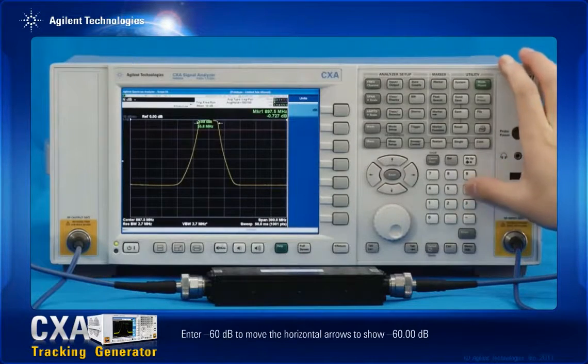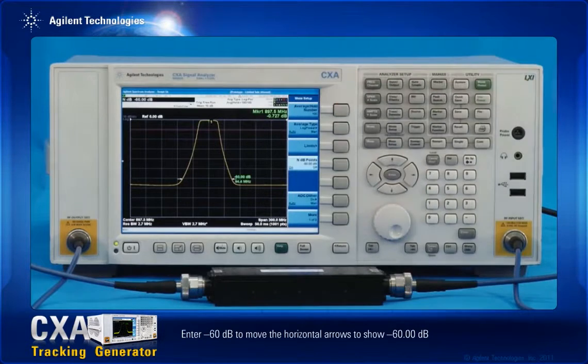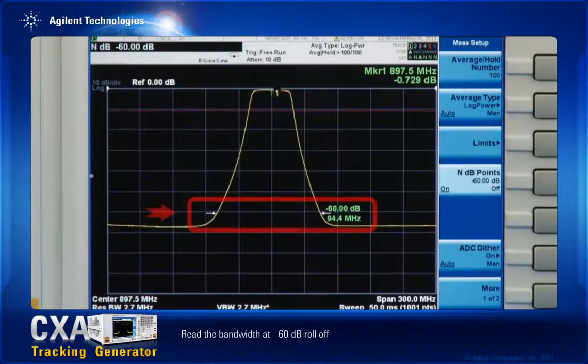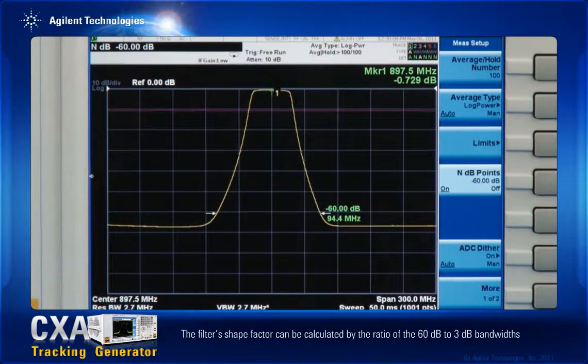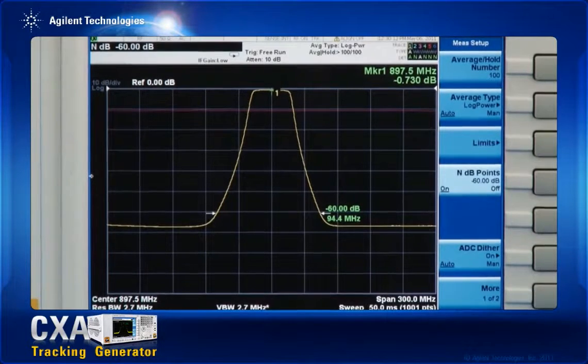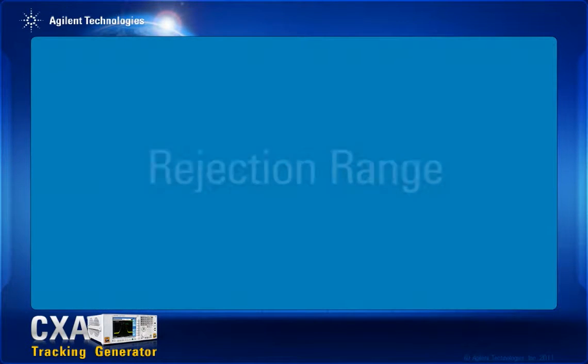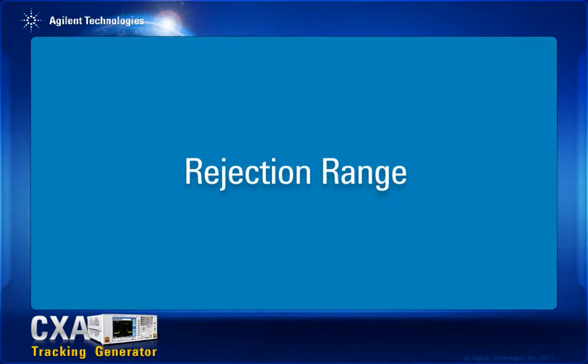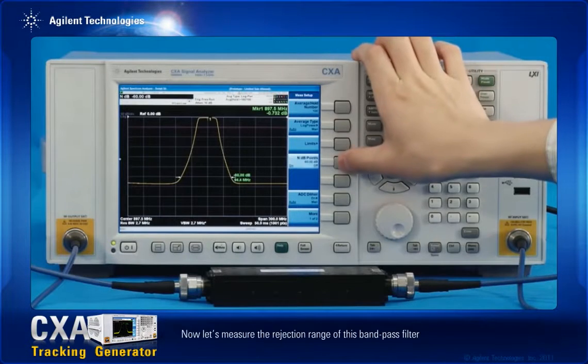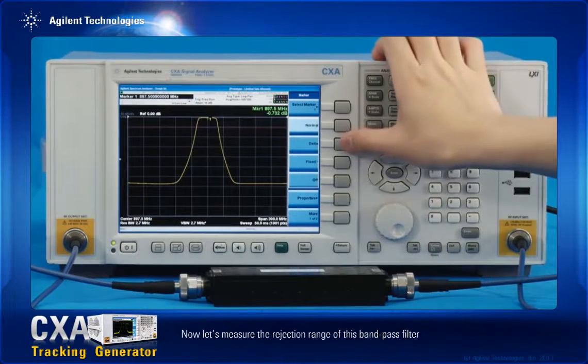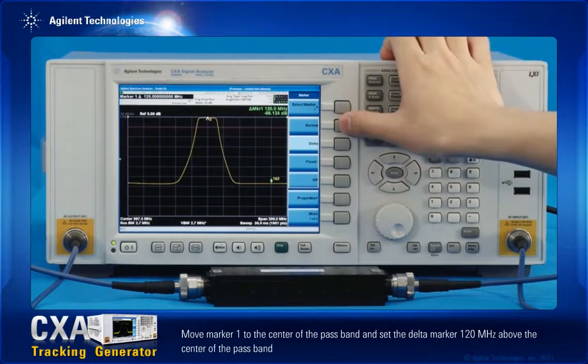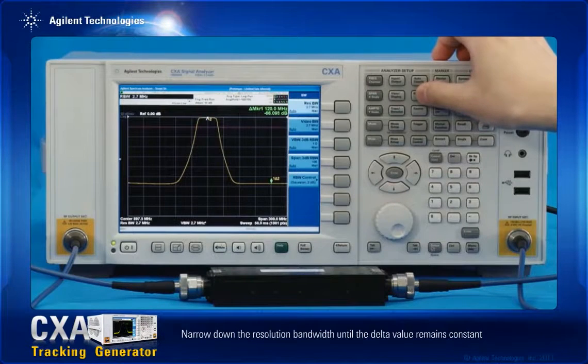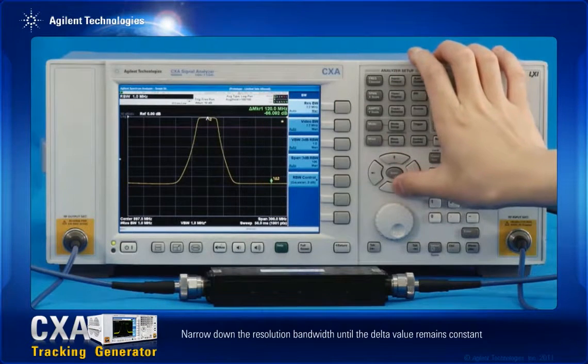Enter minus 60 dB to move the horizontal arrows to show minus 60 dB and read the bandwidth at minus 60 dB roll off. The filter's shape factor can be calculated by the ratio of the 60 dB to 3 dB bandwidths. To measure the rejection range of this bandpass filter, move marker 1 to the center of the passband and set the delta marker 120 MHz above the center of the passband. Narrow down the resolution bandwidth until the delta value remains constant.